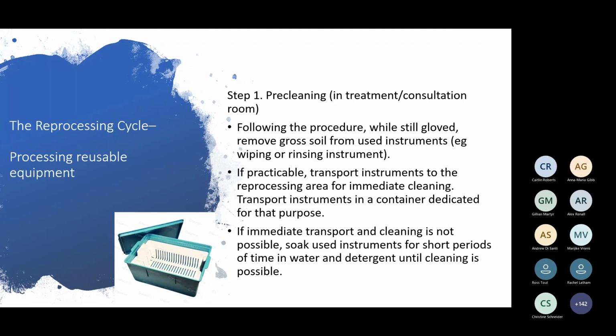If practicable, transport instruments to the reprocessing area for immediate cleaning. Transport instruments in a container designated for that purpose. So if you're transporting instruments from room to room, they should be in a container with a sealed lid. You shouldn't be transporting them in an open container because there's a risk of dropping them, damaging the instruments, sharps injuries, all sorts of things. So if you're transporting from room to room, they need to be in a container with a sealed lid.